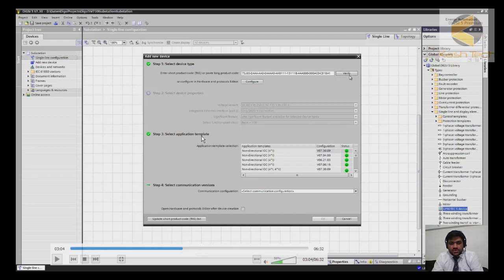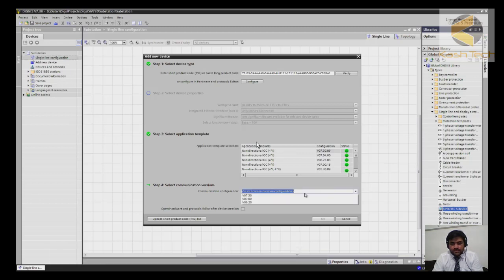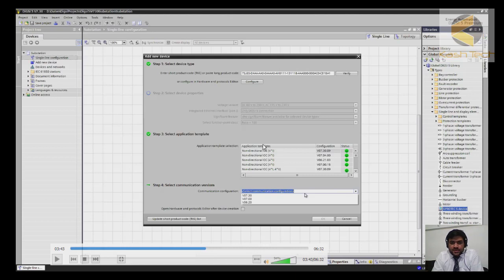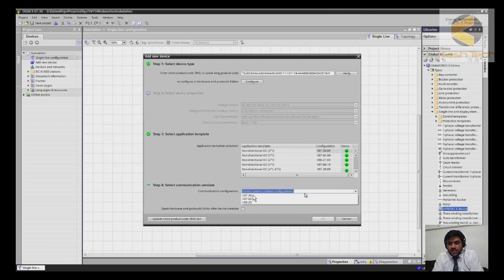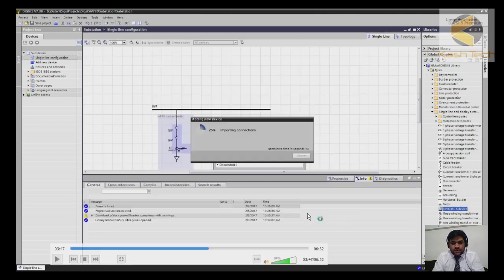If the product code is valid, you will get further access and see Select Application Template, where several functions are available. For example, I will select the non-directional overcurrent configuration, version 7.3009. You also have to select the communication configuration from the ordering information. After that, press OK and DIGSI will start preparing the configuration.